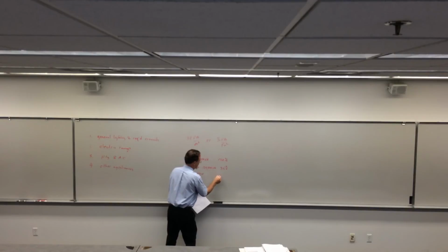Okay, that's fair enough. Now, for 3,000 volt amps to 120,000 volt amps, it's 35%. Well, that's a jump, isn't it? And if you go over 120,000 volt amps, it's 25% of that remainder. Now, why do you bring that up? Why am I crazy like this? Born that way.